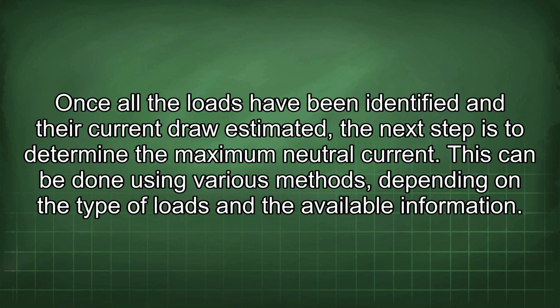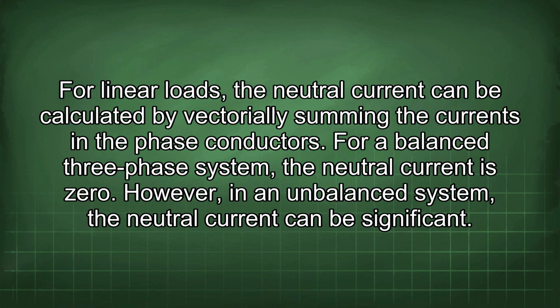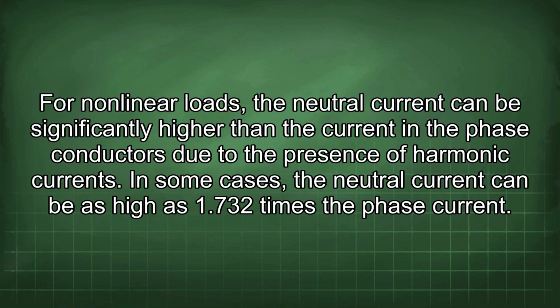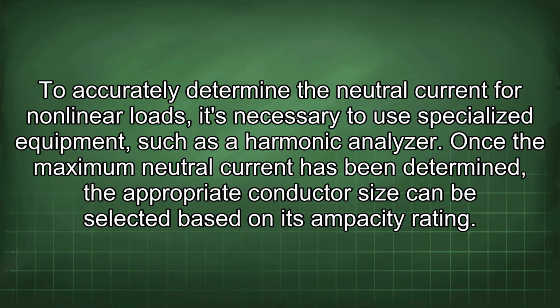Once all the loads have been identified and their current draw estimated, the next step is to determine the maximum neutral current. This can be done using various methods depending on the type of loads and the available information. For linear loads, the neutral current can be calculated by vectorially summing the currents in the phase conductors. For a balanced three-phase system, the neutral current is zero. However, in an unbalanced system, the neutral current can be significant. For nonlinear loads, the neutral current can be significantly higher than the current in the phase conductors due to the presence of harmonic currents. In some cases, the neutral current can be as high as 1.732 times the phase current. To accurately determine the neutral current for nonlinear loads, it's necessary to use specialized equipment, such as a harmonic analyzer.